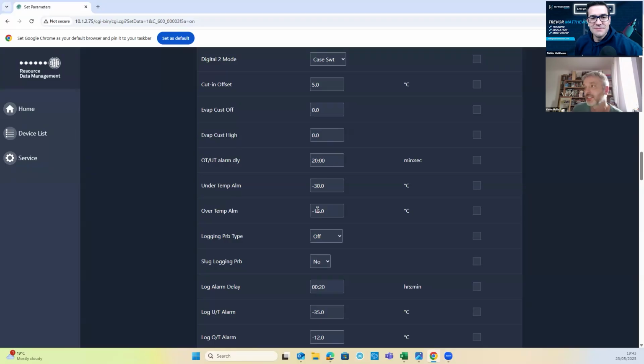If you're doing a customer that hasn't got a spec, you're an engineer. You know how high that fixture is going to realistically go during normal operation, and it's going to depend what it is. Let's take a popular one. If it's the cafe cold store in a Costco, let's say, that door during trading is going to be open 11.5 hours out of 12, right? So if it's a freezer and you set that for -15, it's going to spend the whole day in alarm.